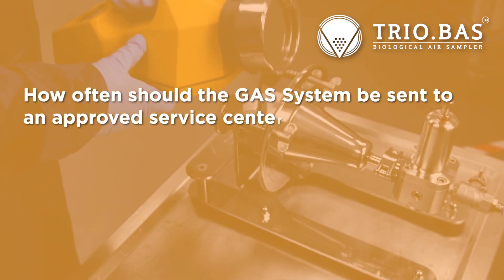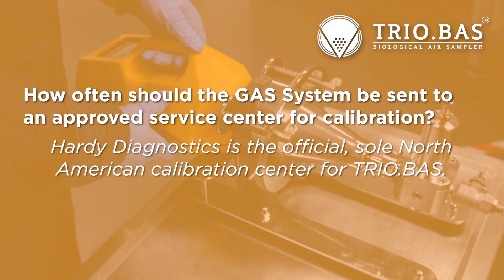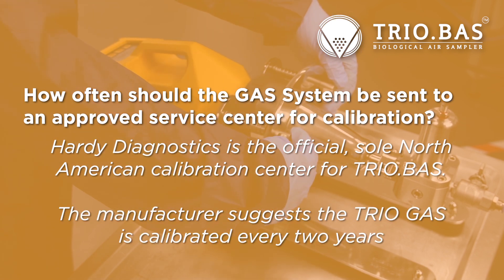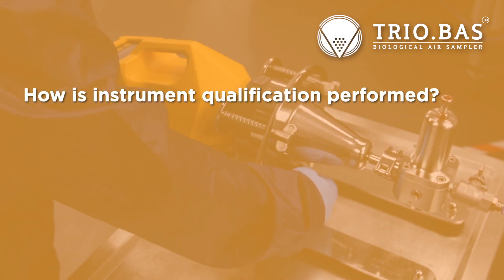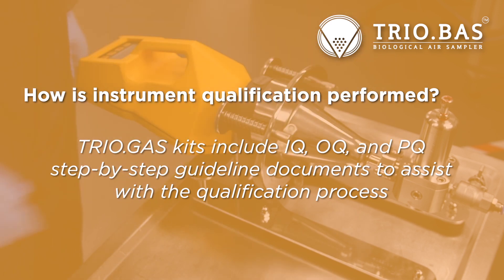How often should the gas system be sent to an approved service center for calibration? Hardy Diagnostics is the official, sole North American calibration center for TRIO.BAS. The manufacturer suggests that the TRIO gas is calibrated every two years. How is instrument qualification performed? TRIO gas kits include IQ, OQ, and PQ step-by-step guideline documents to assist with the qualification process.